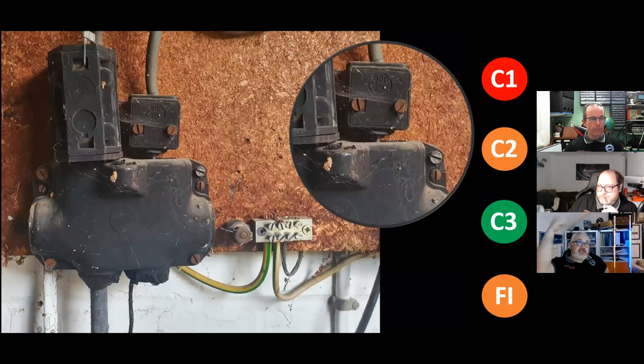This is the last one. This is to tease the DNO one we're going to do. So this is a wonderful old DNO head. It's one of the old paper insulated, lead wrapped conductors. You can see from it there's an earthing conductor coming out the bottom. There's actually two of them. One went down to a clamp on the lead sheath. The other one came out of the side of it. But if you look carefully at the circle, you can see an exposed conductor where somebody has obviously changed that neutral connection over the years. This is normally filled with pitch as an insulating compound or an alleged insulating compound.